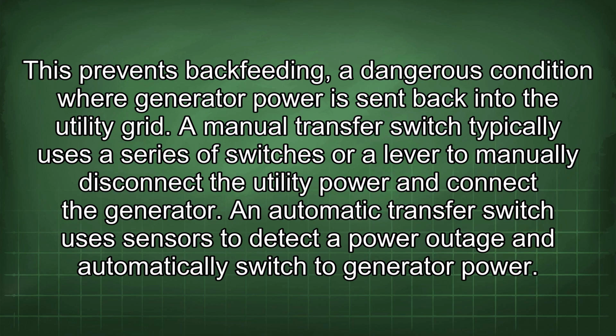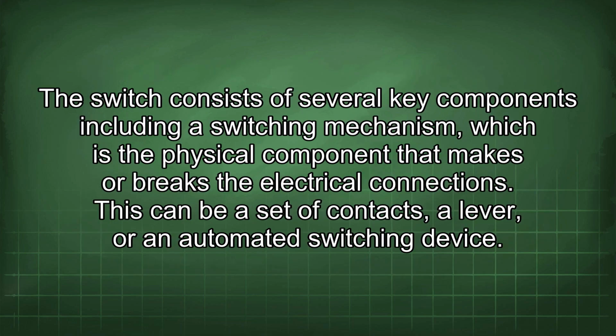A manual transfer switch typically uses a series of switches or a lever to manually disconnect the utility power and connect the generator. An automatic transfer switch uses sensors to detect a power outage and automatically switch to generator power. The switch consists of several key components, including a switching mechanism, which is the physical component that makes or breaks the electrical connections. This can be a set of contacts, a lever, or an automated switching device.